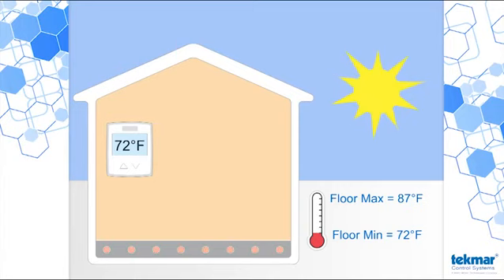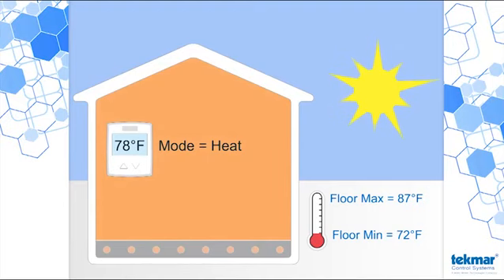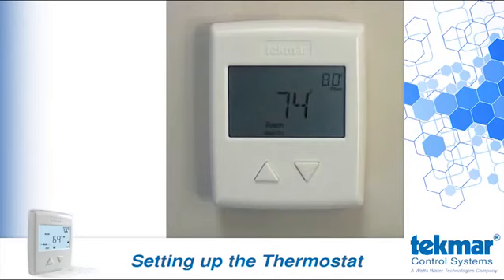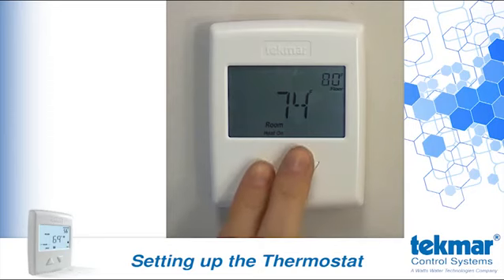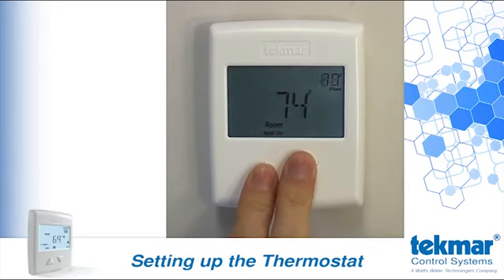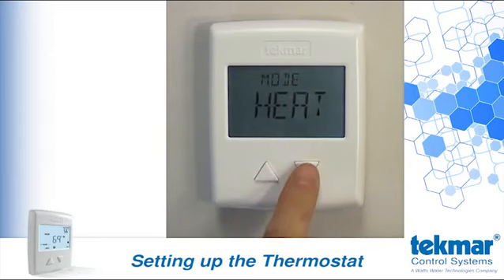It is important to realize that the floor minimum setting will always be in effect as long as the mode is set to heat. This may inadvertently cause overheating in the summer when floor warming is undesired. To disable floor warming, it is necessary to set the thermostat mode to off. There are 2 ways to turn the mode off. You can do so in the first area of adjustment, where mode is the first setting that you see. Use the down button to set it off.